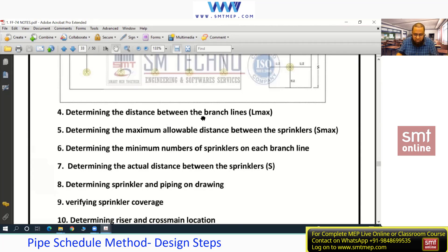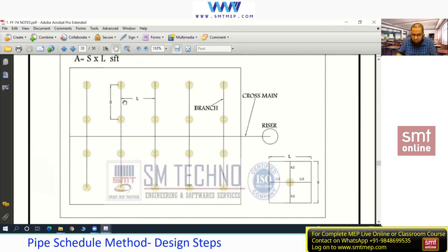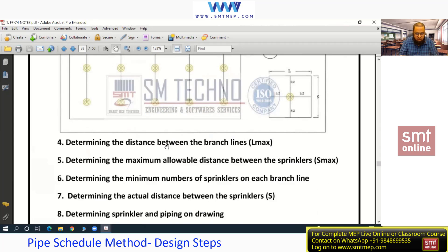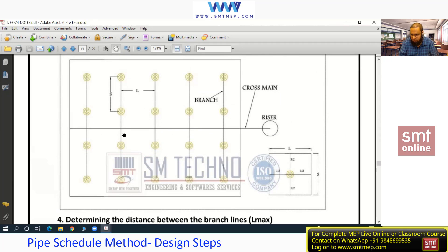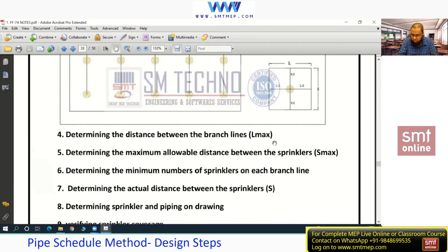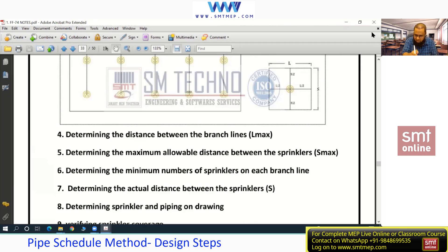Step 4: Determine the distance between the branch lines — this is the L dimension. Branch line again refers to the construction lines, not the branch pipes. I'll draw horizontal and vertical construction lines. Step 5: Determine the maximum allowable distance between sprinklers — the S dimension. Note L max and S max from the code: for light and ordinary hazard, this is 15 feet. Based on site conditions and uniform arrangement of sprinklers, we find actual S and actual L.